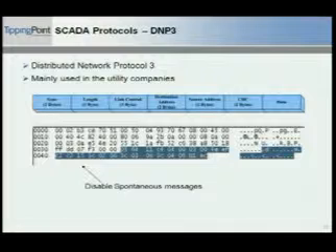But a funny thing happens in the DNP3 protocol: after every 16 bytes of data, a 2-byte CRC is added. And they have a different kind of CRC, called CRC DNP3, and I have that one implemented too if someone requires it. It's available outside too. The next one is the link control, which ensures that your communication is going on fine, and then the destination address, source address, the CRC and the data.